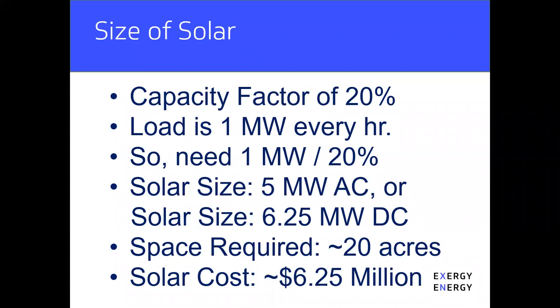All right, how much solar do we need? First thing to start with is the capacity factor for solar, sort of average in the United States, is about 20%, meaning it's only generating at its capacity about 20% of the time. In the middle of the night, the solar's not doing anything for you. Your load, again, this is going to be a water treatment plant—our load is 1 megawatt every single hour. So essentially we've got 24 megawatt hours that we need to generate with solar that only has a 20% capacity factor.